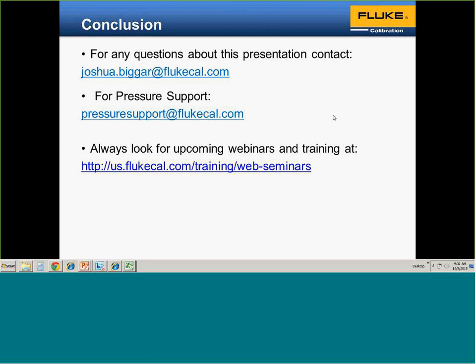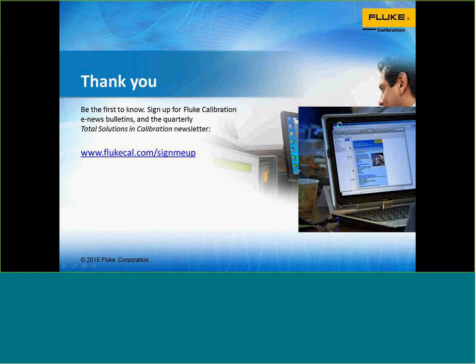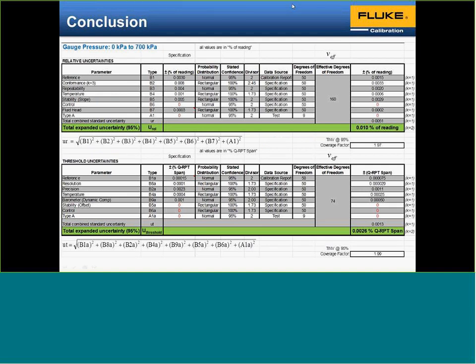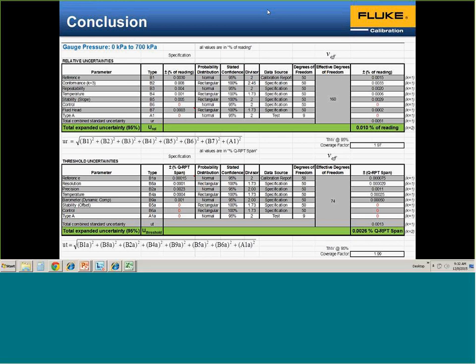The first question we have is about threshold uncertainty. Is it given as a percent of range, or percent of full scale, or percent of reading? Can you walk through the threshold uncertainty concept again? Okay, this is commonly referred to as a floor error, and this is not an adder. It's a percent of reading or a percent of span, whichever is greater.